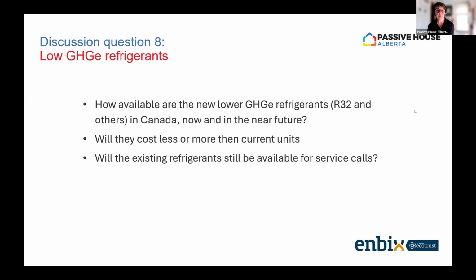The first opinion was interesting on the VRV and R32 stuff, because I somewhat agree but totally disagree. I do a lot of VRV, VRF too—it's a big part of my business. On the transition from 410A to R32 on the Daikin VRV in particular, you don't really have to worry about the whole transition. The piping is fully backwards compatible, so in 15 years, if you have to replace the equipment, the 410A piping works 100% with the R32 stuff. Replacement indoor and outdoor units would be available for the next 10 years, at least from Daikin.